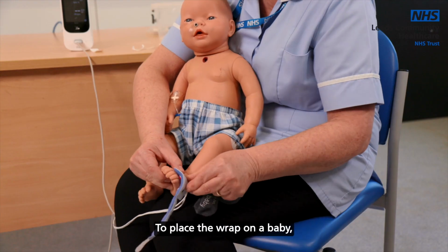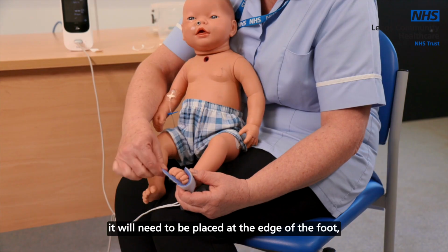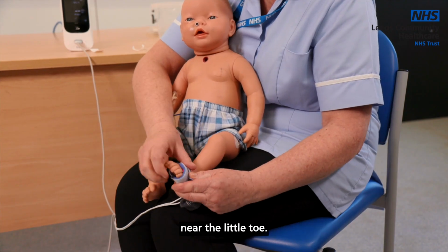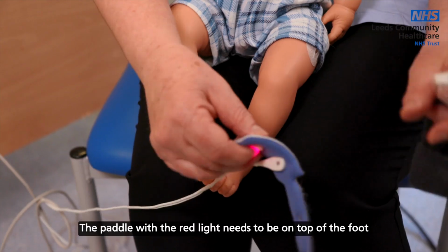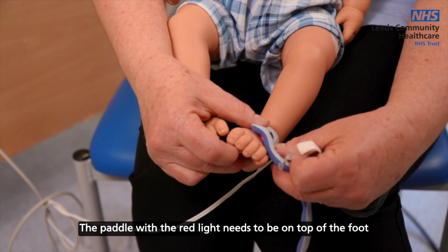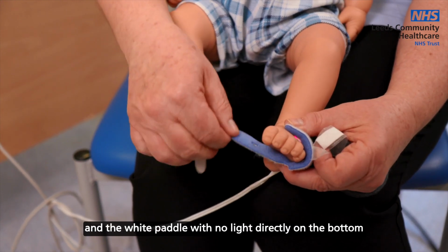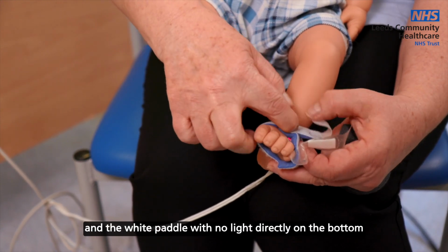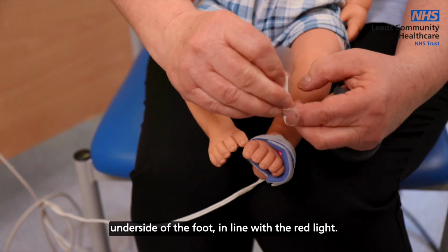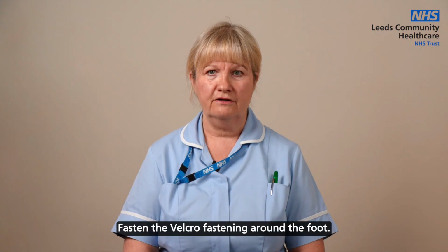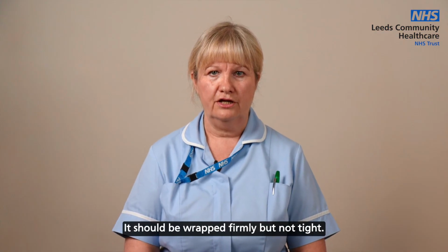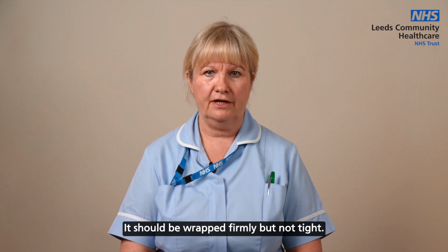To place the wrap on a baby, it will need to be placed at the edge of the foot near the little toe. The paddle with the red light needs to be on top of the foot and the white paddle with no light directly on the bottom underside of the foot, in line with the red light. Fasten the Velcro fastening around the foot. It should be wrapped firmly but not tight.